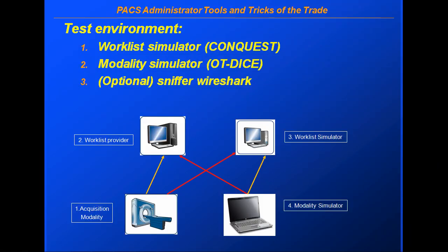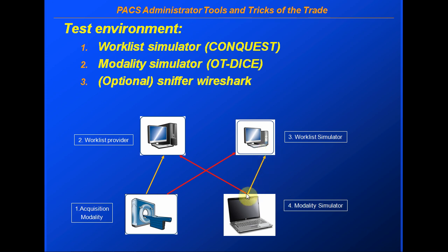A typical test environment consists of two components — here's my CT scanner and here's my modality worklist provider, which is my clinical system. I want to create a test environment that has a modality simulator and a worklist simulator. I can go from my regular modality to my worklist simulator to see what's going back, or I can have another modality talking to my worklist provider to find out exactly what's going on.